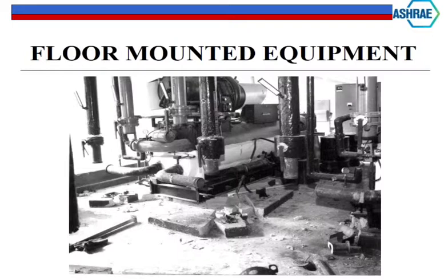One of the other problems is all of these connections here, they all ripped out, right? Those are where flex connectors could have been put there and saved this, and moved with it and not broke. So what happens when all this water breaks? All these connections break on all these chillers.